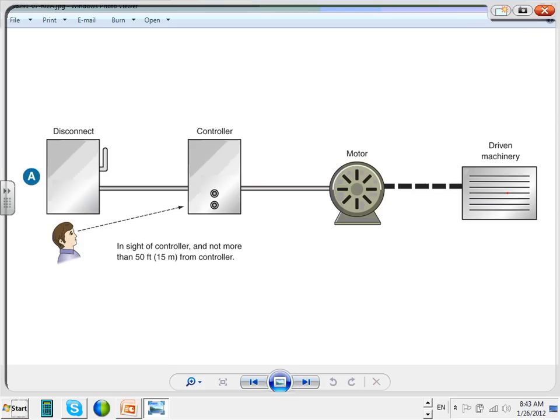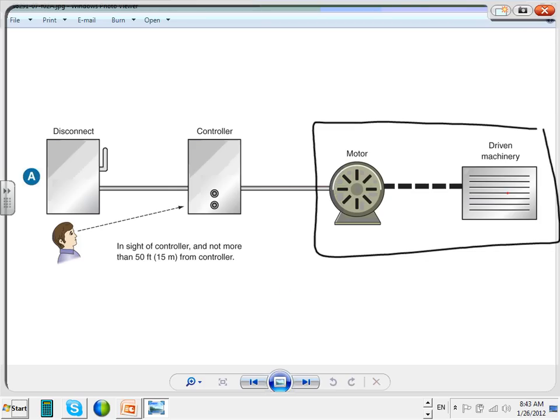So when we have a motor, I want you always, please, every time you think of a motor, think of the machine that's going to be driven by this motor. This machine could be right next to the motor, coupled to it, or it could be 10, 20, 30, 40 feet away from this motor, connected with a V-belt or with a gear or whatever. Okay, so that's the most important thing about this picture, understanding that motors always drive machines. Then, for safety, we talked about, guys, that this disconnect that you're looking at has to be within sight of the motor, the machine, as well as the controller.